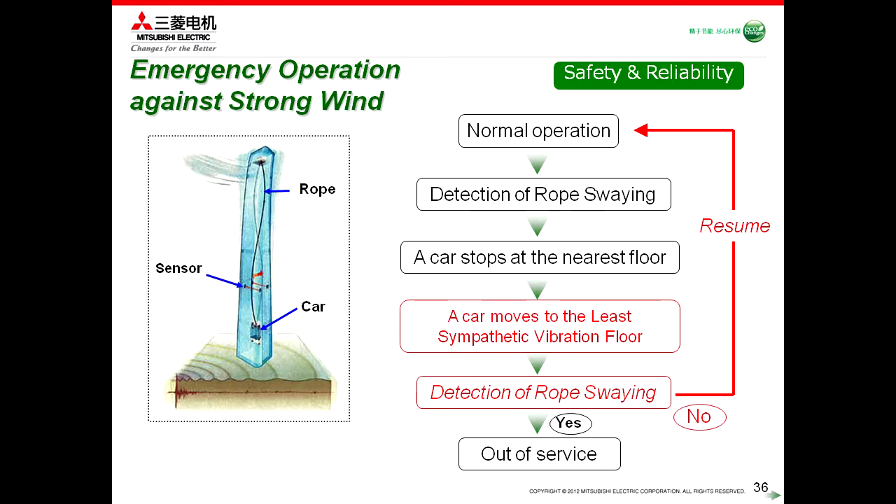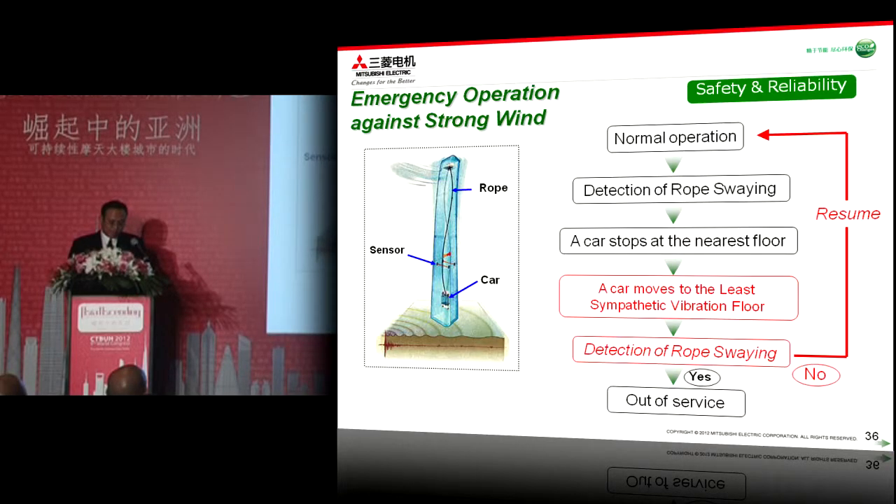For such high rise buildings, the influence of strong wind should be well considered, as well as earthquakes. However, strong wind conditions occur more often than earthquakes. How to maintain elevator service level against strong wind is one of the key issues to overcome. Therefore, we developed a rope sway detection system detected by sensors installed into the shaft. After passenger evacuation at the nearest floor, once rope sway is detected, the elevator stations at the least sympathetic vibration floor, detecting rope swaying twice during a certain period. Then, if no rope swaying is detected, the elevator can resume normal operation automatically.